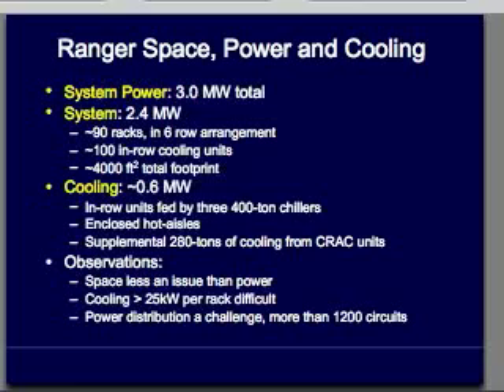Just to show some pictures of the deployment. I mentioned we have 3 400-ton chillers, just to get a sense of the size, there's your basic 18-wheeler dropping this thing off. It's all built to have N+1 redundancy, so that's why there's 3 of them. It only takes 2 to cool the system at one time, with the only caveat being that there are a few days in August when it gets really hot in Texas, and there's a good chance all 3 will be on. So we might have to limit the queues a little on those days.